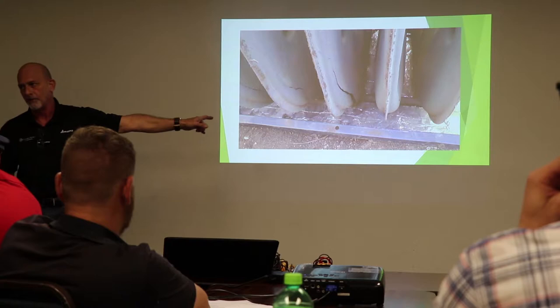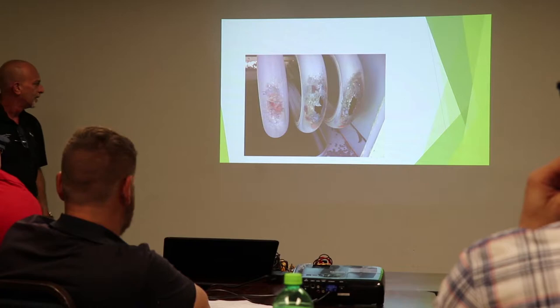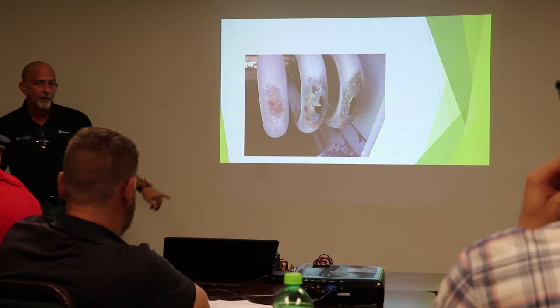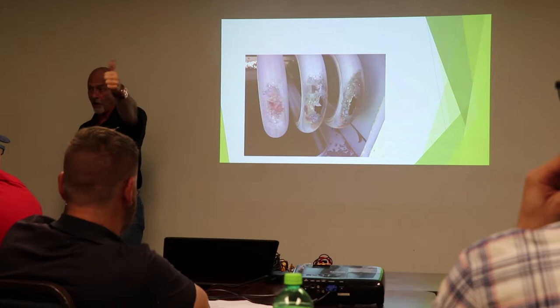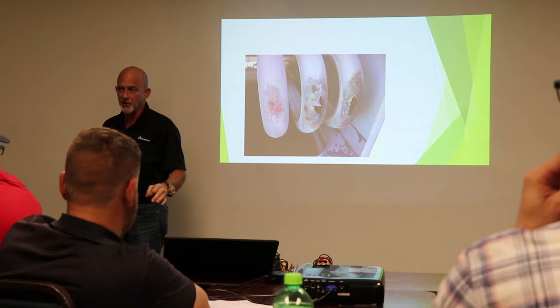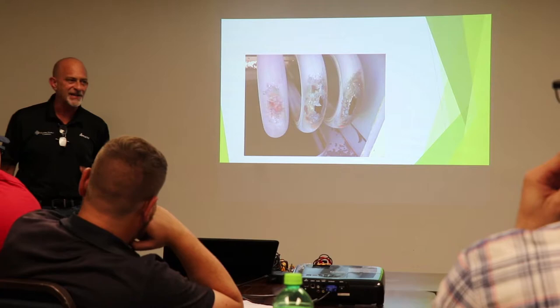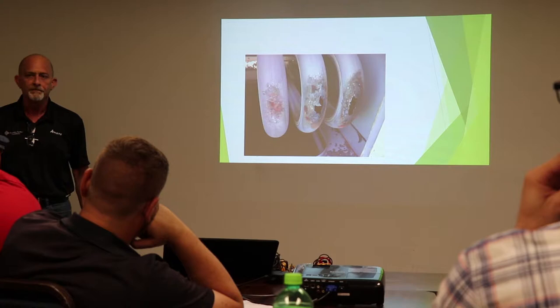That's another heat exchanger. That's a rooftop unit. Now, how do we get things like this? Too much heat. Too much heat, right? Airflow. Also, manifold gas pressure. And I'll talk a little bit more about manifold gas pressure. Has anybody seen a gas valve increase by not touching it? It can do it.